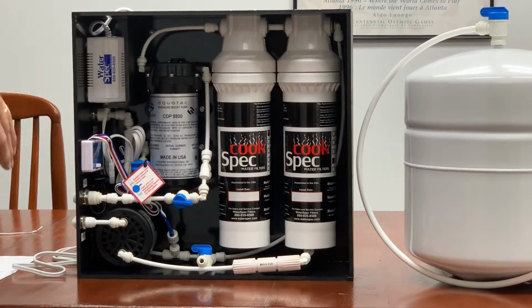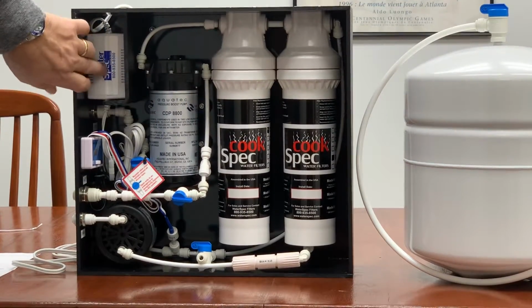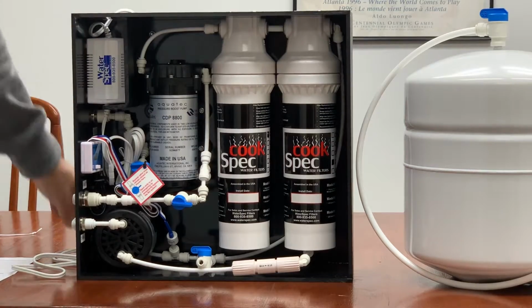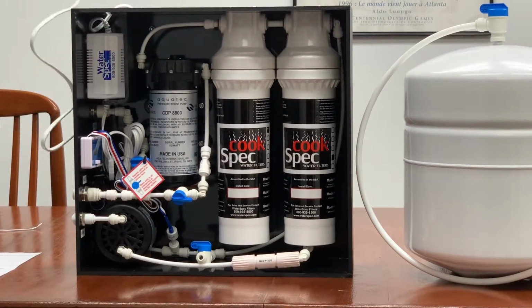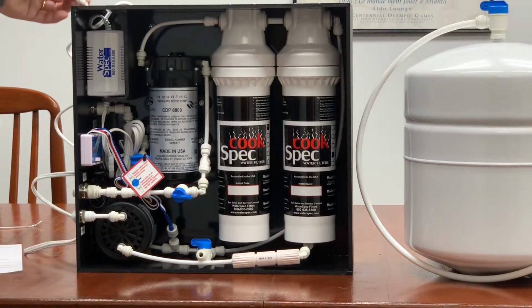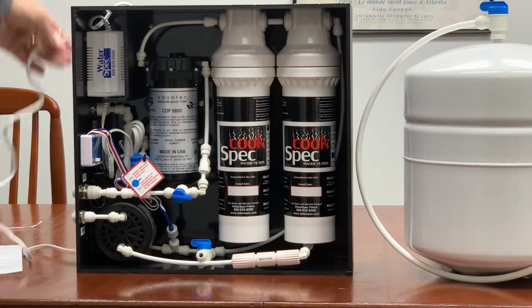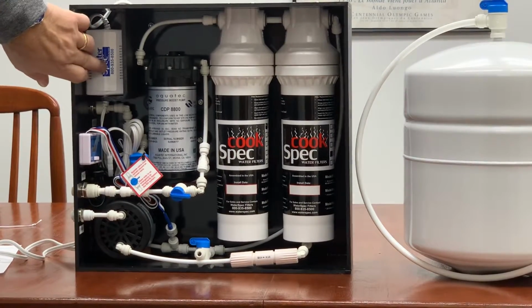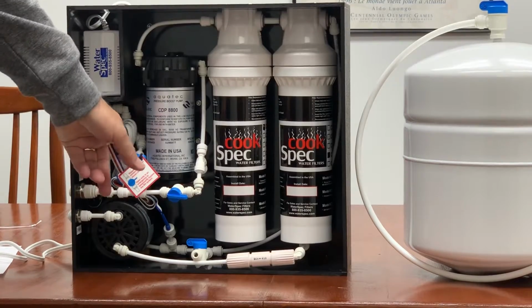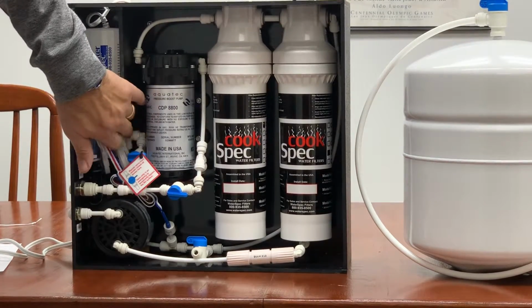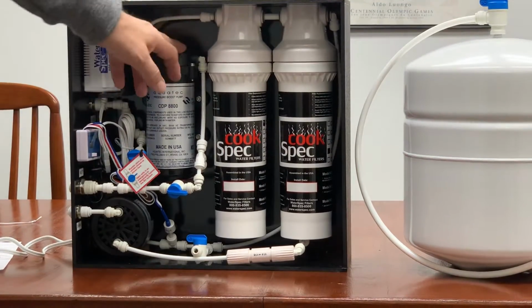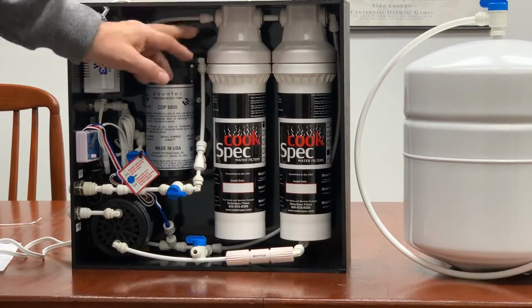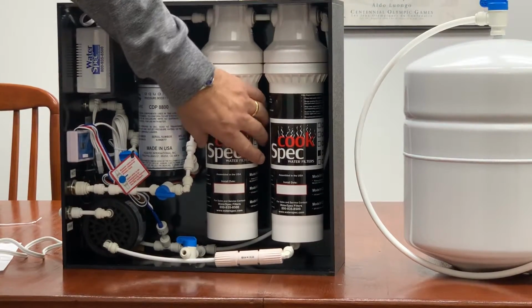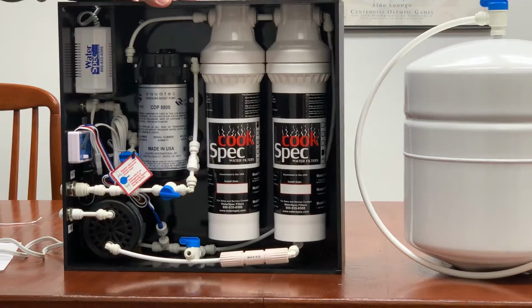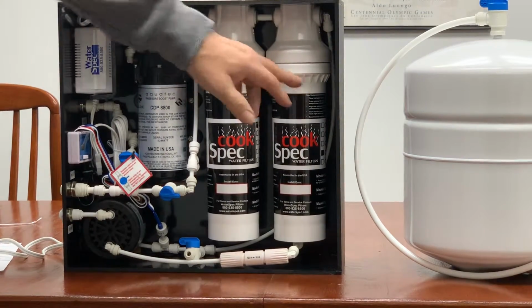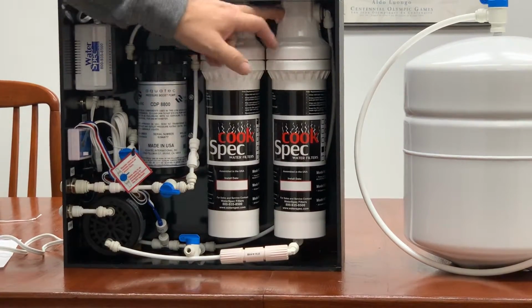Okay, the booster pump is powered by this transformer, which plugs into the wall, roughly 6 foot of cord. If you need to plug into a farther extension, you can always remove the transformer, mount it externally, and you have another 5 feet of cord here. So from the booster pump, you have water that goes to the inlet of the primary cartridge. The primary cartridge removes chlorine, sediment, protects the RO membrane. From the primary cartridge, we go into the membrane.